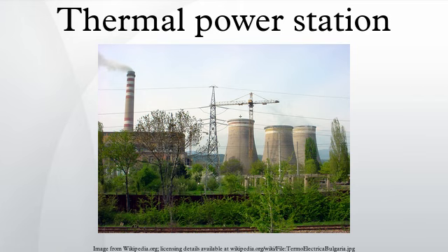Where required by law, the sulfur and nitrogen oxide pollutants are removed by stack gas scrubbers which use a pulverized limestone or other alkaline wet slurry to remove those pollutants from the exit stack gas. Other devices use catalysts to remove nitrous oxide compounds from the flue gas stream. The gas traveling up the flue gas stack may by this time have dropped to about 50 degrees Celsius. A typical flue gas stack may be 150–180 meters tall to disperse the remaining flue gas components in the atmosphere. The tallest flue gas stack in the world is 419.7 meters tall at the GRES-2 power plant in Ekibastuz, Kazakhstan. In the United States and a number of other countries, atmospheric dispersion modeling studies are required to determine the flue gas stack height needed to comply with the local air pollution regulations.